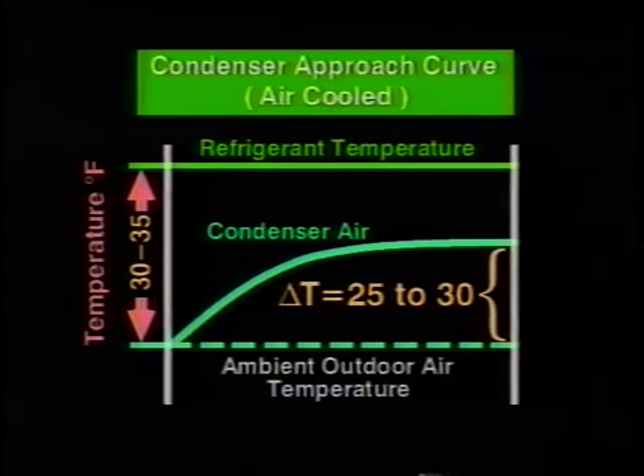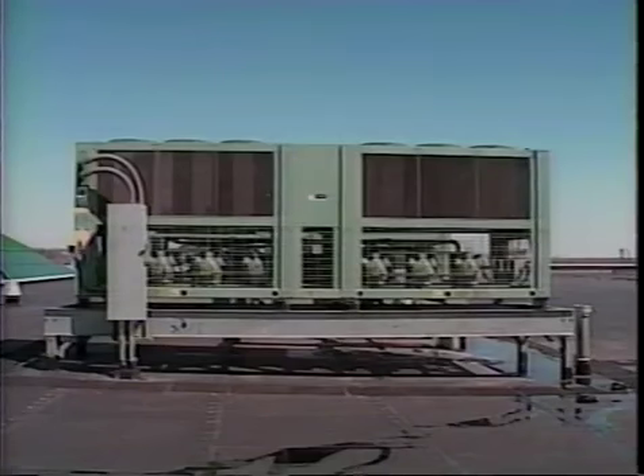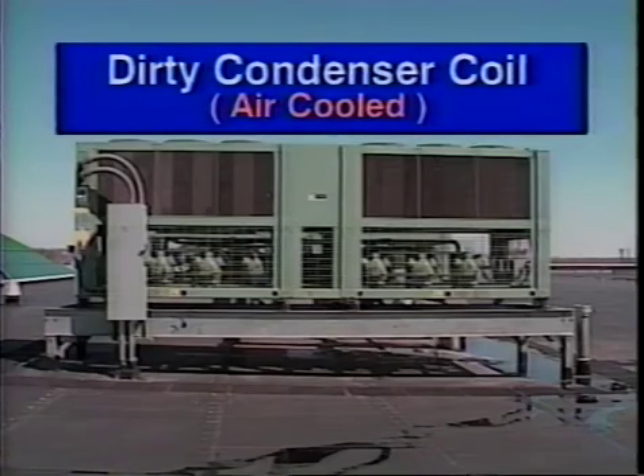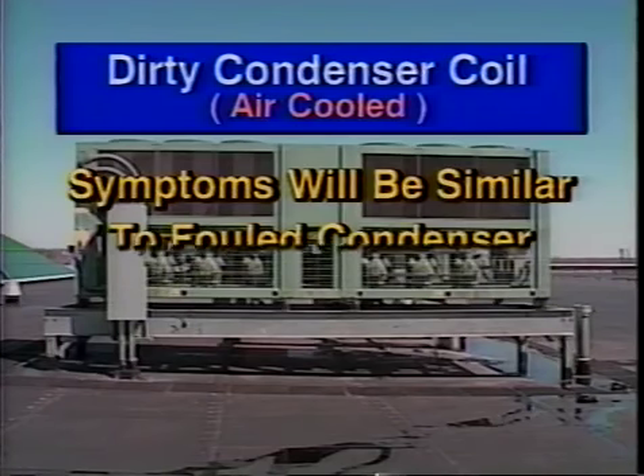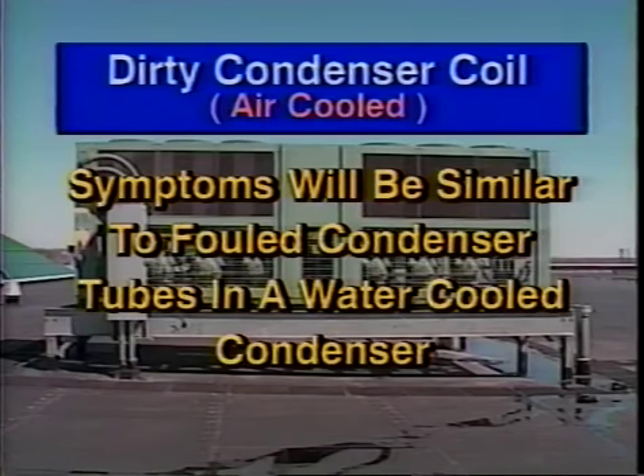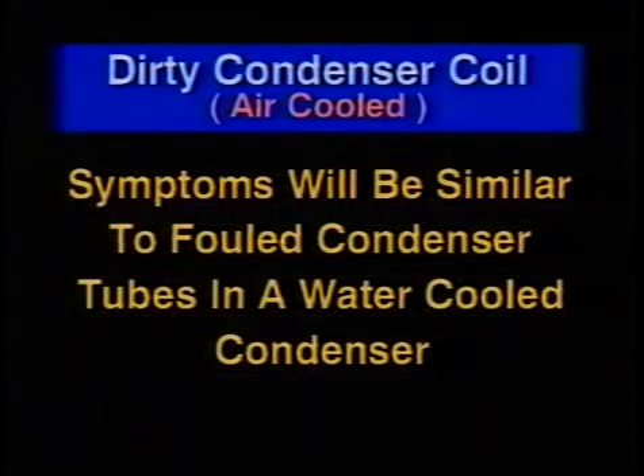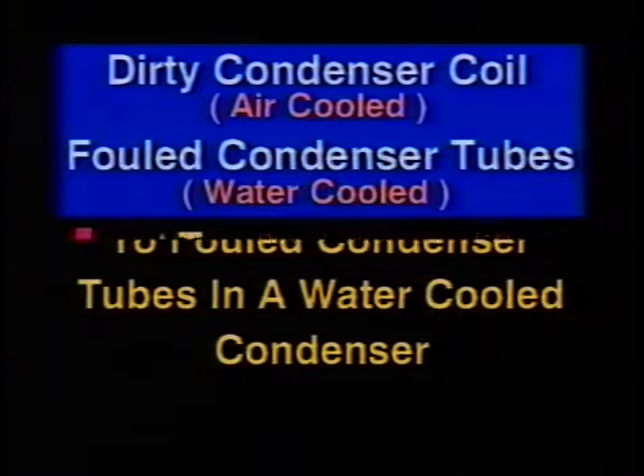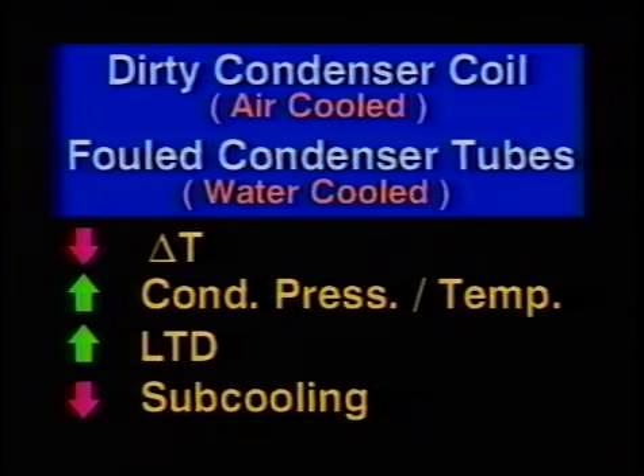For instance, if the condenser coil is dirty and is restricting airflow, the heat transfer from the refrigerant to the air will be impeded. The symptoms will be similar to those of fouled condenser tubes in a water-cooled condenser. The symptoms for both condensing mediums, air or water, would include a decrease in delta T across the condenser, an increase in condensing pressure and saturated condensing temperature, an increase in LTD, and a decrease in subcooling.